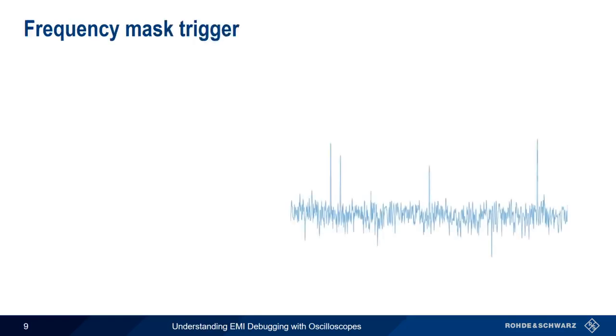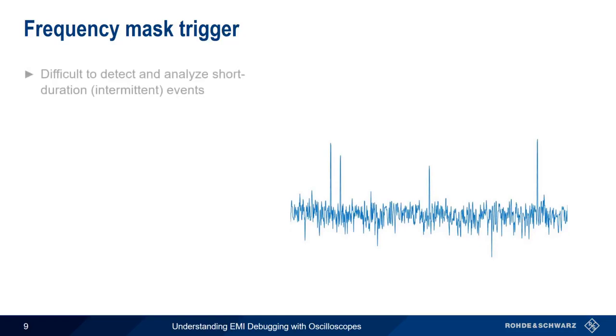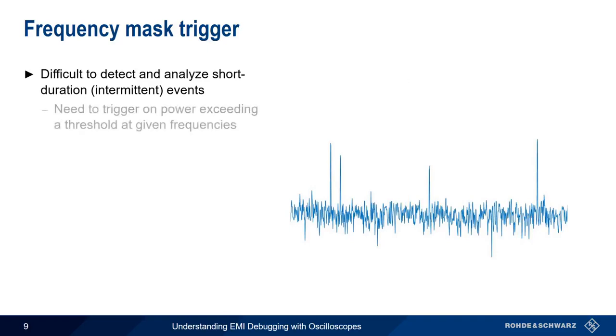Some EMI issues involve undesired or spurious signals that are continually present, but many issues involve intermittent signals that are difficult to detect and or analyze. One way of resolving these types of issues is to trigger on a power that exceeds a user-defined threshold at a given frequency or over a given frequency range. This is unlike normal oscilloscope triggering based on voltage changes over time.